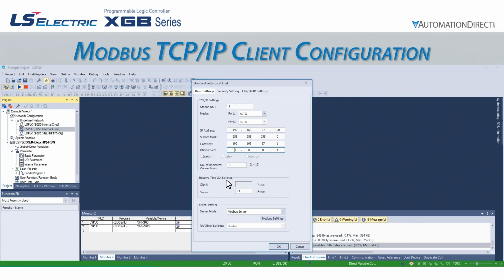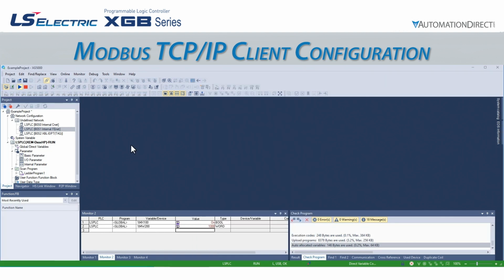If we are using the PLC as a Modbus client, we need to verify the number of dedicated connections field has been set to something less than 16 to allow our client to occupy one of the Modbus connections. Ours is set to the default of 3, and we won't be setting up more than 13 client connections, so that number is fine. Now we need to set up a peer-to-peer connection for the internal FENet network.